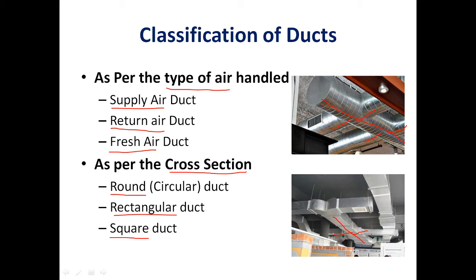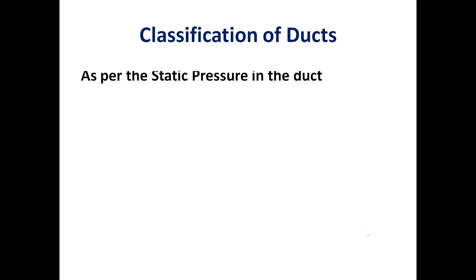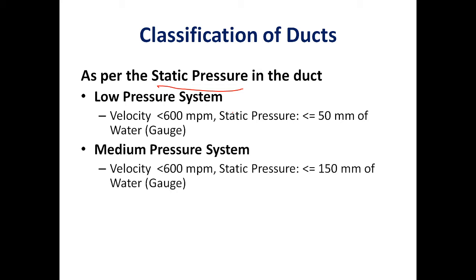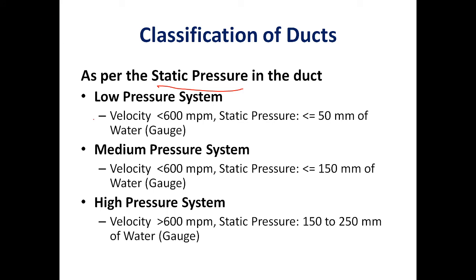The third classification is based on static pressure inside the duct. The system is divided into three classes: low pressure, medium pressure, and high pressure. In a low pressure duct system, the air velocity is limited to 600 meters per minute and the static pressure is up to 50 mm of water column.